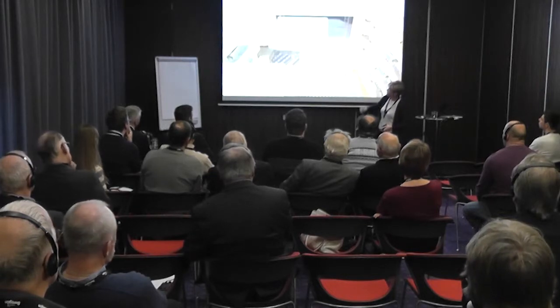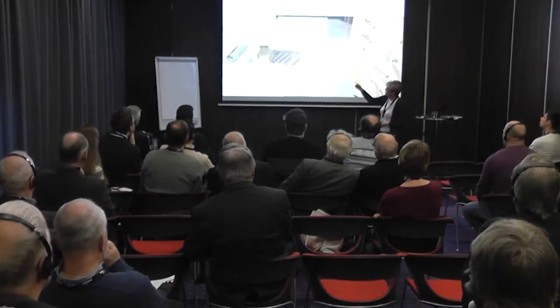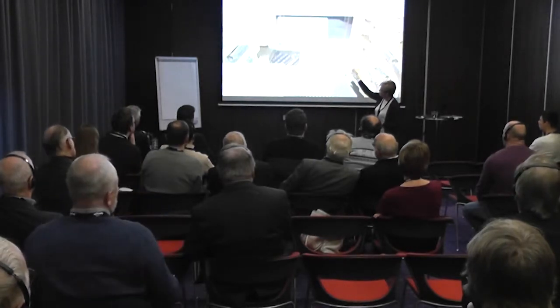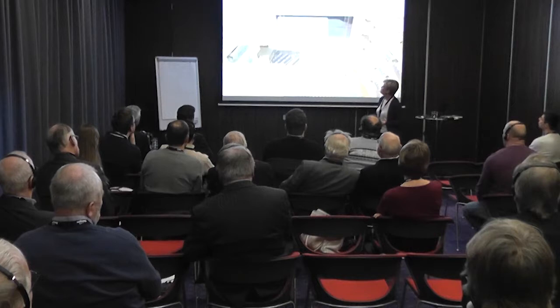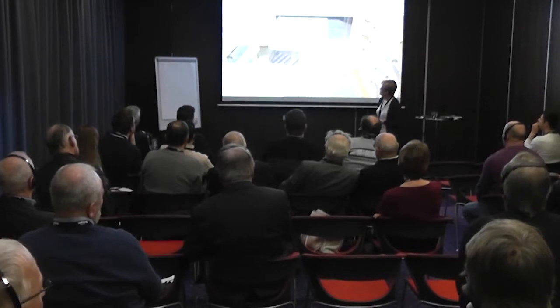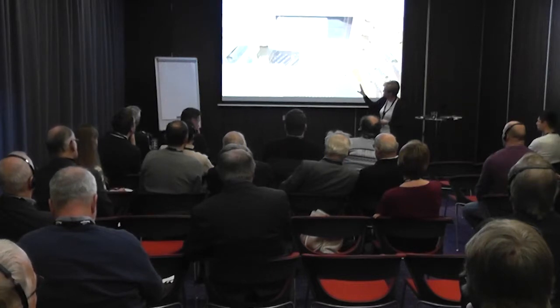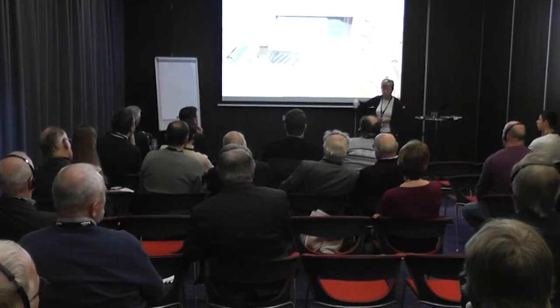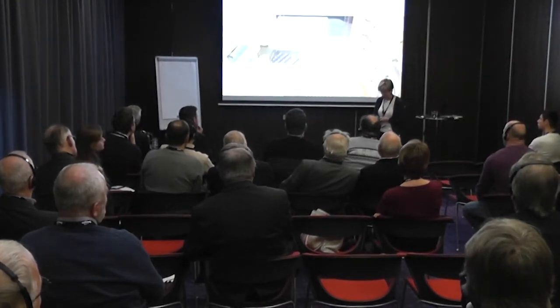They get the supply on the floor. And up on the left is a system that supplies air to the stage. Here you see the supply to the stage is divided into one area for the stage and one area for the warm-up for the singers. So they can have different humidity in these areas. And all these systems should work together. And of course they have rotary heat exchangers, and they have humidification, all of the systems.